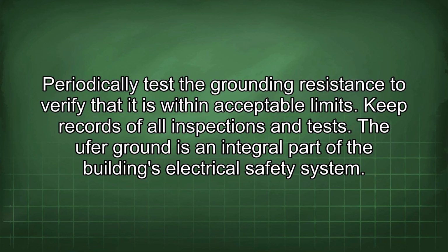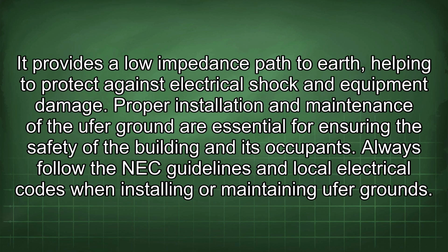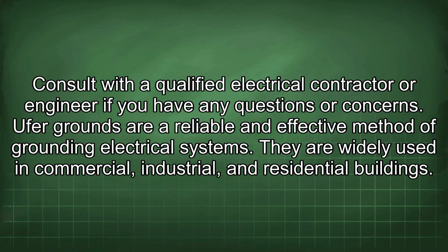The Ufer ground is an integral part of the building's electrical safety system. It provides a low impedance path to earth, helping to protect against electrical shock and equipment damage. Proper installation and maintenance of the Ufer ground are essential for ensuring the safety of the building and its occupants. Always follow the NEC guidelines and local electrical codes when installing or maintaining Ufer grounds. Consult with a qualified electrical contractor or engineer if you have any questions or concerns.